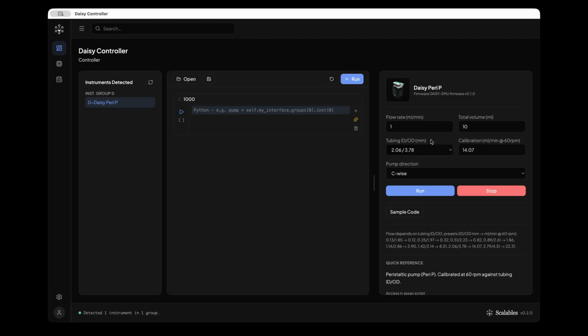As an example, tubing installed here has a 1.14 mm ID with a 2.86 mm OD, which autofills the predicted calibration to 3.9 mL per minute at 60 RPM. Pump direction can be switched between clockwise and counterclockwise.